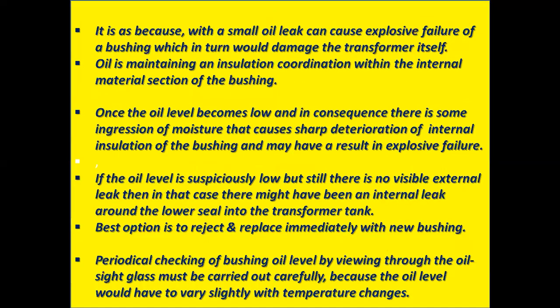This is because even a small oil leak can cause explosive failure of the bushing, which in turn would damage the transformer itself. Oil maintains insulation coordination within the internal material section of the bushing. Once the oil level becomes low, and in consequence there is some ingression of moisture, it causes sharp deterioration of the internal insulation of the bushing and may result in explosive failure.